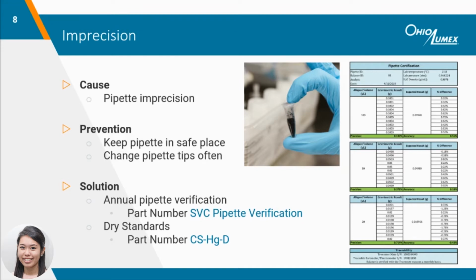If the pipette is accurate but it is still difficult to create a linear calibration, the pipetting technique may need to be refined. Since the technique can be difficult to master, we created dry standards for those who don't perform analysis frequently, minimizing the time spent on creating a good calibration.